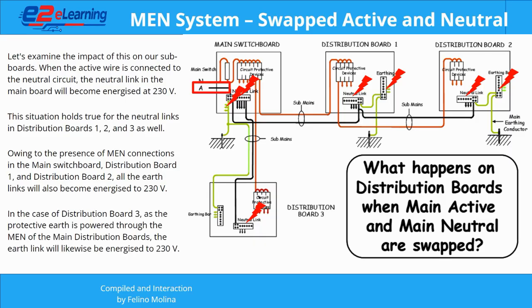In the case of distribution board 3, as the protective earth is powered through the MEN of the main distribution boards, the earth link will likewise be energized to 230 volts. This presents an extremely hazardous scenario that you certainly want to avoid within your switchboard, as this state will endure as soon as power is supplied to the switchboard.